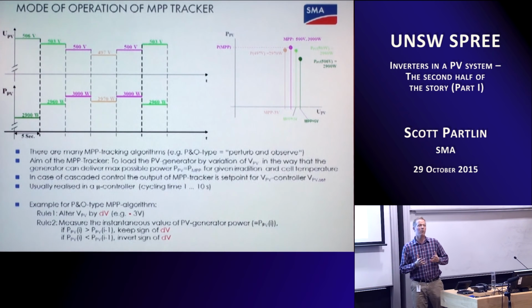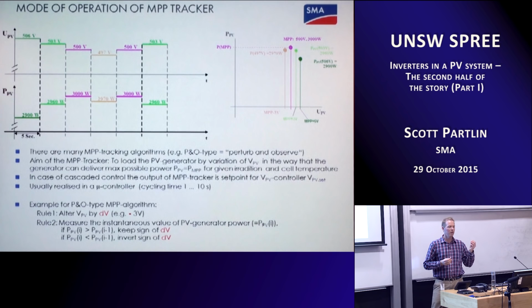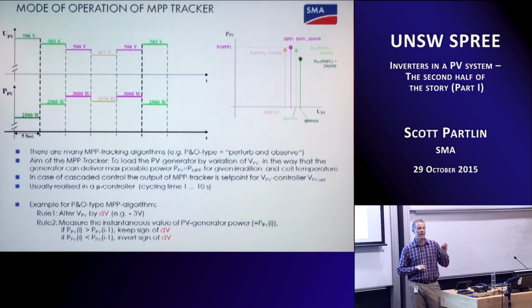But that's not what happens in real life, the sun varies constantly. If you've been on the roof with an insolation measurement device, you'll notice your watts per metre squared goes up and down all the time, and that impacts each PV module differently, and how that affects a PV string is different too. So this process is happening continually. Clouds pass, and we might slide all the way down the curve, and the inverter needs to recognise events like that and respond, always bringing the output of the PV array back to its maximum.